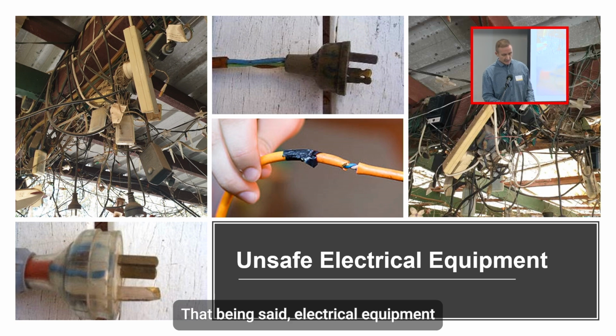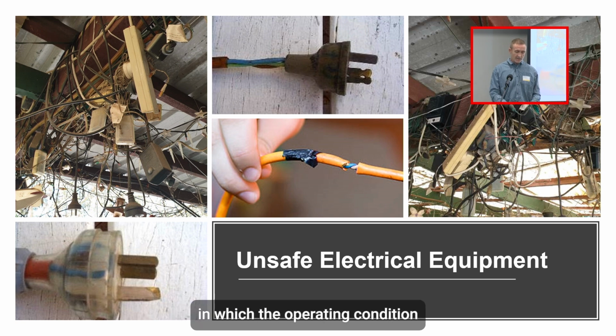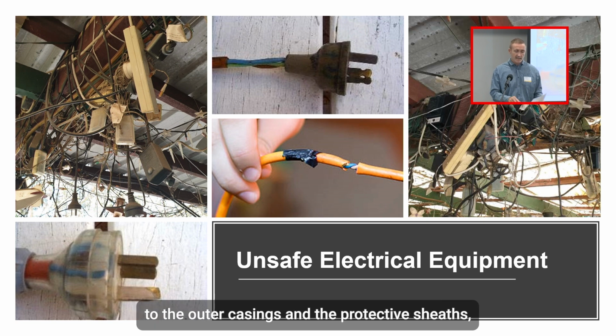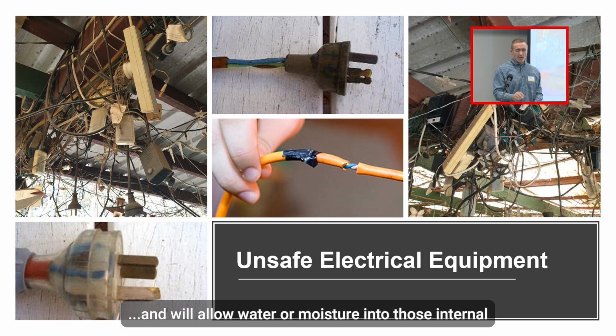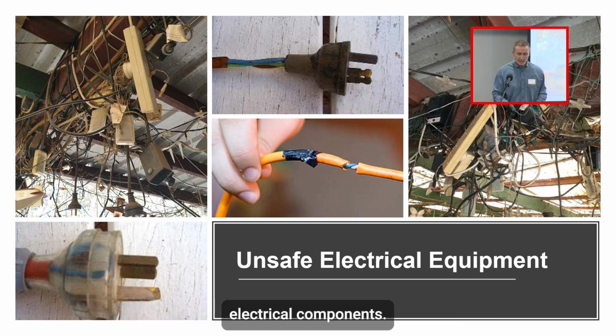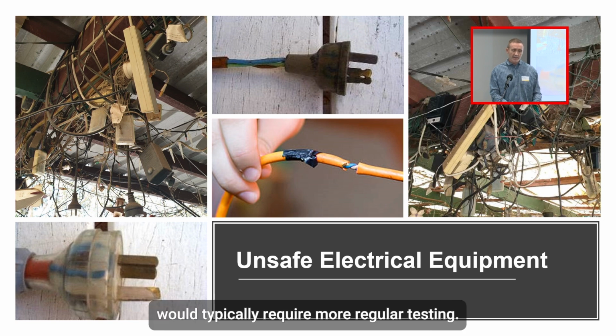That said, electrical equipment used in environments where operating conditions are likely to cause damage or reduced lifespan, including moisture, heat, vibration, mechanical damage, corrosive chemicals, etc., could develop cracks and damage in the outer casings and protective sheaths, allowing water or moisture into the internal electrical components. Obviously, these environments would typically require more regular testing.